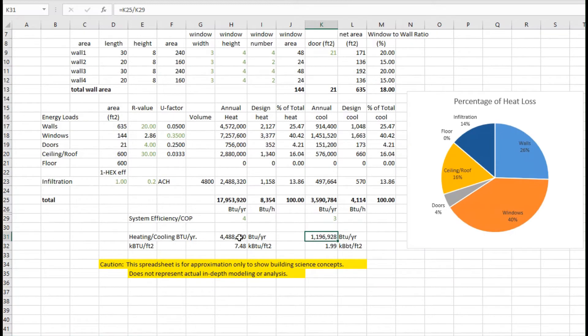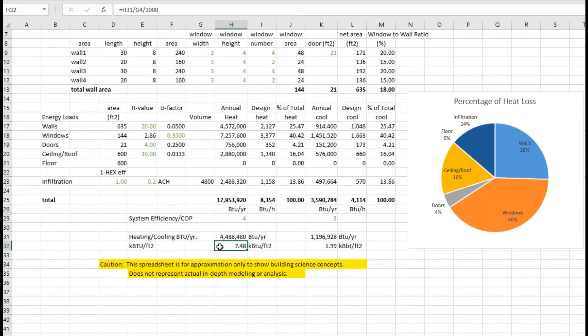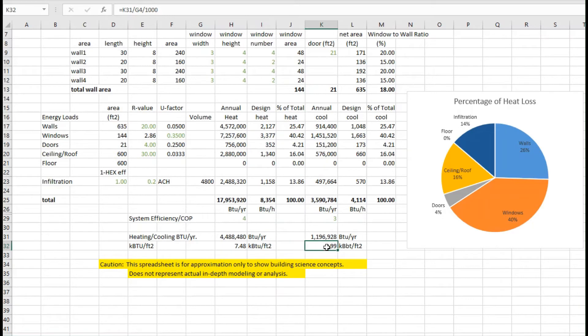I can take that number and normalize it against the size of the building. That helps me compare buildings to buildings, and compute how many thousands of BTUs per square foot, or the energy use intensity we need for heating, and we need for cooling.